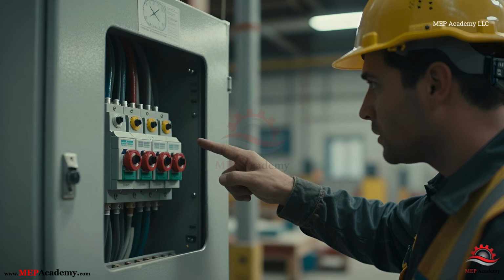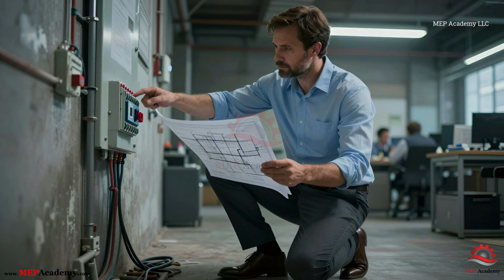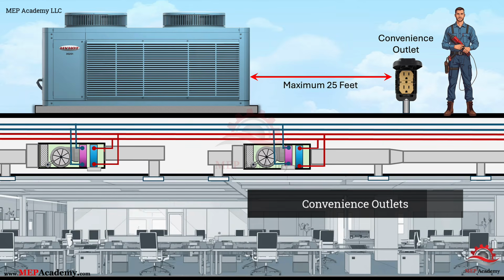This issue frequently appears when equipment arrives on site and no disconnect has been provided, resulting in additional cost and schedule impact. Proper coordination requires confirming the disconnect type, rating, and mounting location early in the project, along with who is responsible. The third issue involves convenience outlets and service receptacles near mechanical equipment.